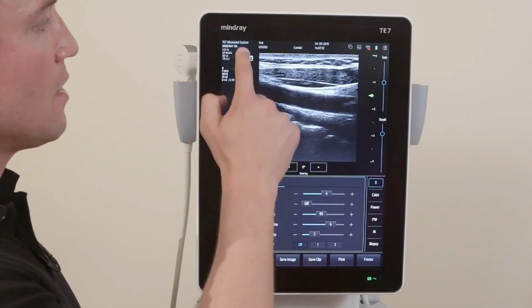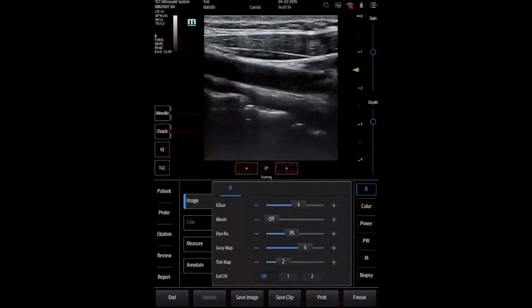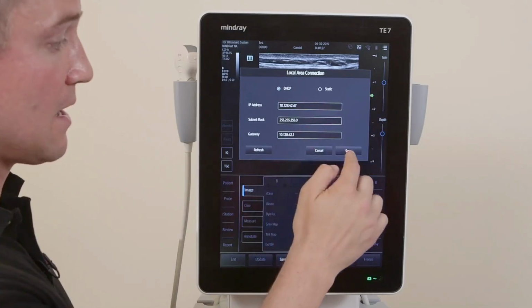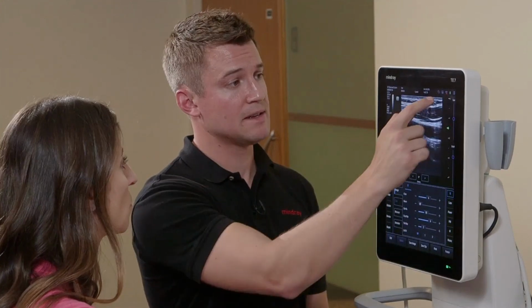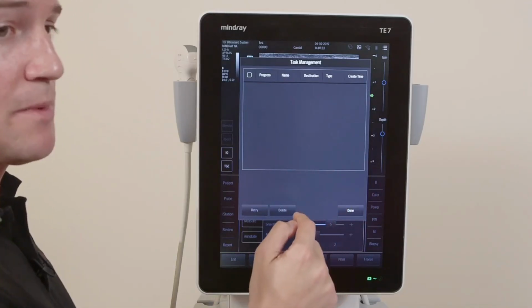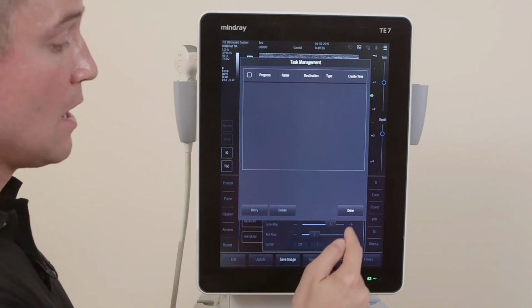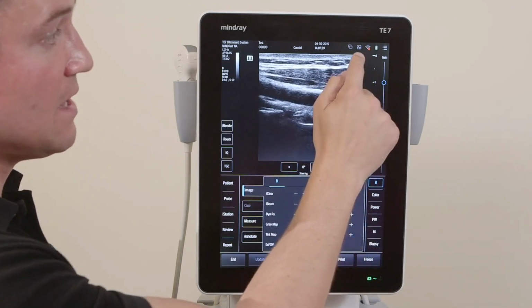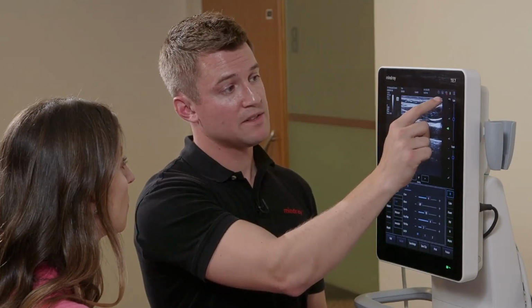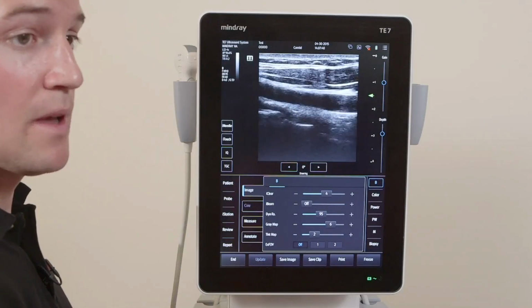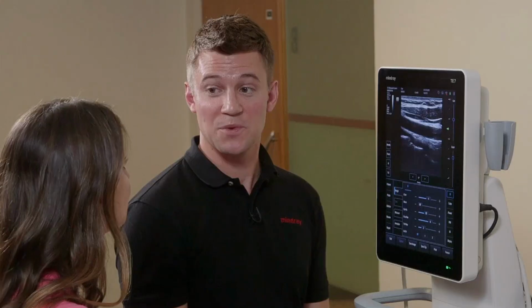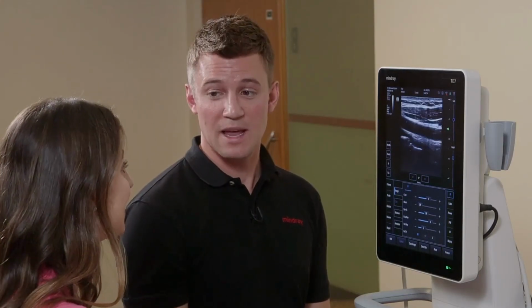Up on the top of our image along the top panel, the status bar, you want to look at a couple of things. If I select these icons, this will show us where we're connected to an IP address for work list and sending to server, and you can choose a dynamic connection or a static. I'll go ahead and cancel out of here since we're, again, not connected. The other option is it shows your task management for when you're sending to DICOM or you're sending to a USB, other ways of exporting. And then we see if we're connected to Wi-Fi. The TE7 has built-in Wi-Fi, which is really nice. You have your battery icon. The TE7 has about 2 hours of battery time when you're unplugged, and it has a retractable power cord, which makes it really nice for getting around and not having to wind your cable up.